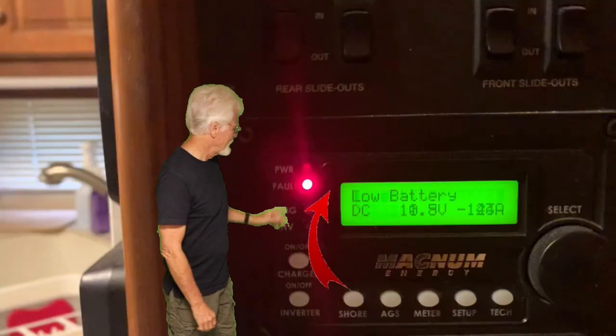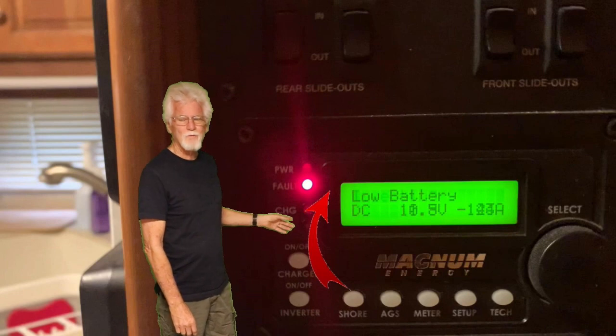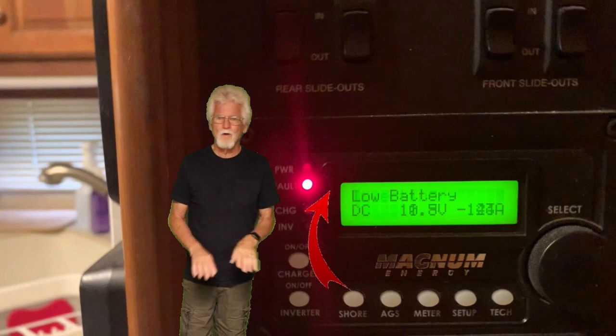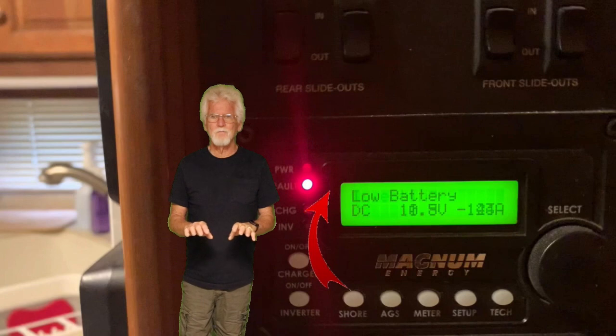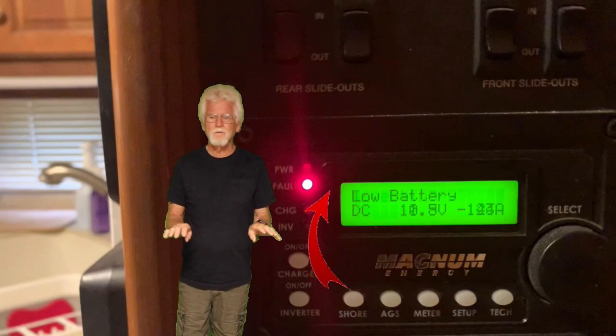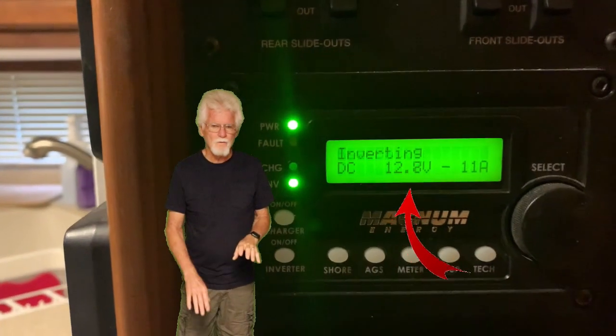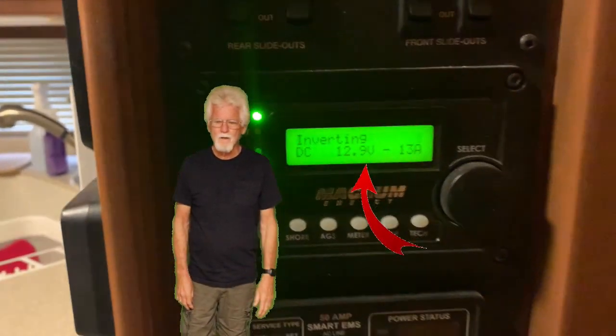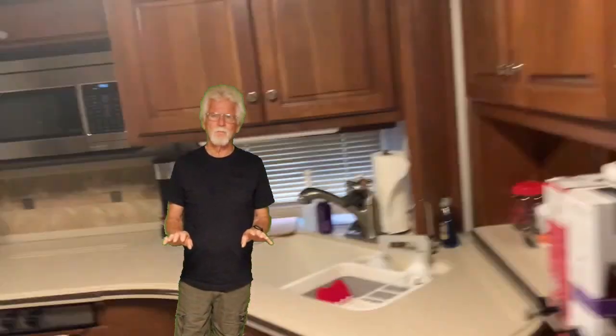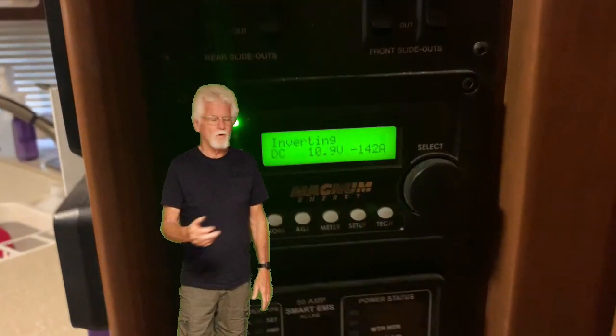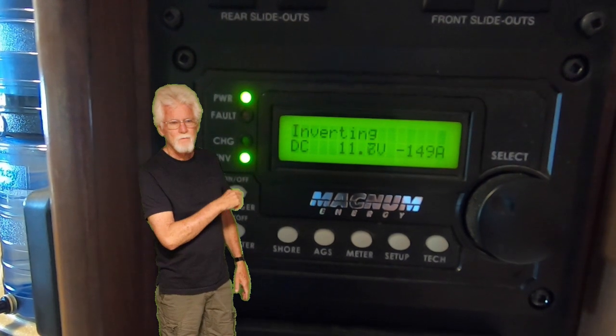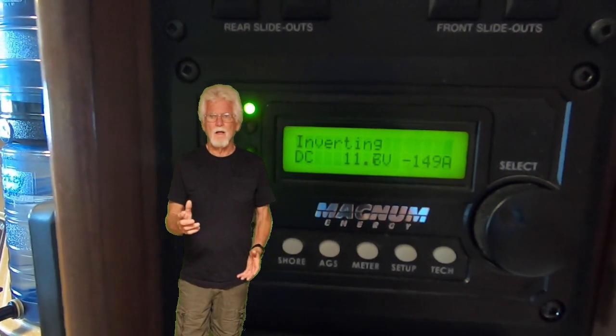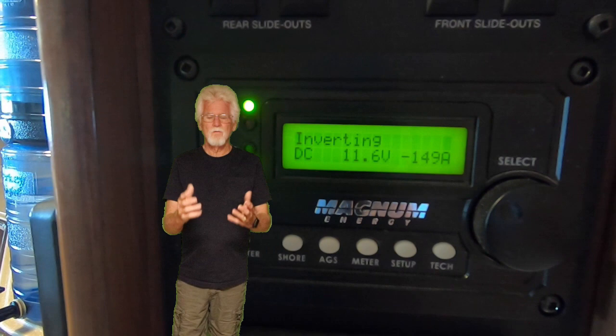Wow, that was quick — the voltage dropped down to 10.5 for a second, which triggered the low voltage alarm. That caused the inverter to shut off all the loads, and once the loads went off, the battery worked its way back up to 12.8. Everything worked just like it's supposed to, and we got our answer: the Dr. Prepare battery can deliver a lot more than the 100 amps it advertises. I saw 145 on the meter, and maybe it could put out even more.